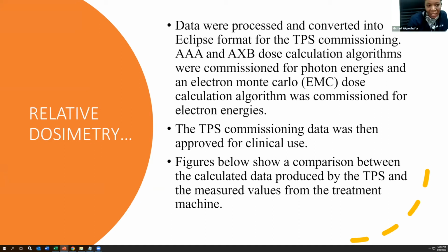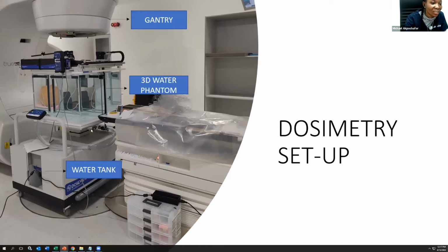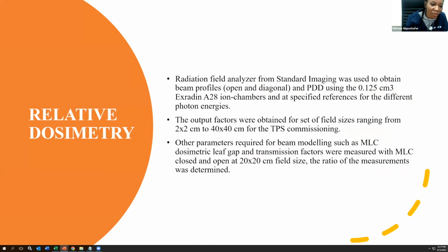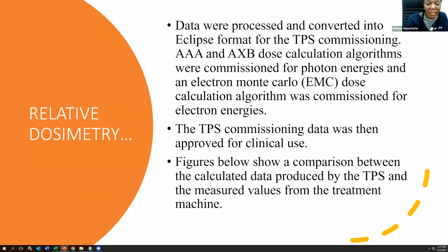Okay, now when all these data are acquired, we convert them into Eclipse format from the dosimetry laptop. Just like I said here, this 3D water phantom is controlled by software, and on the software we input all the things we want to measure. That is how we acquire all those data. Now, this data will be processed and converted into the TPS, the treatment planning system, for commissioning of each of the algorithms. Like I said earlier, we have the AXB, the AAA, and we also have the EMC. So when it is processed, it is converted into Eclipse format, and we process each of these data for the proper commissioning.